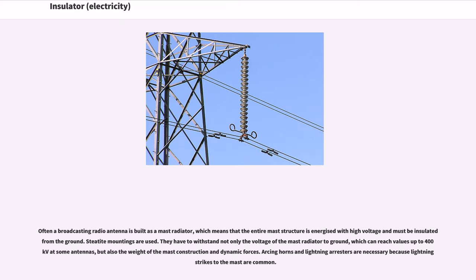Often a broadcasting radio antenna is built as a mast radiator, which means that the entire mast structure is energized with high voltage and must be insulated from the ground. They have to withstand not only the voltage of the mast radiator to ground, which can reach values up to 400 kilovolts at some antennas, but also the weight of the mast construction and dynamic forces. Arcing horns and lightning arrestors are necessary because lightning strikes to the mast are common.